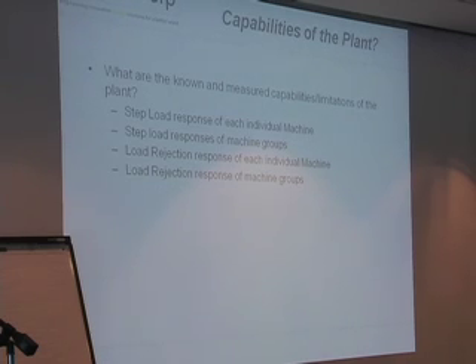And then how do they behave in different groups? We originally didn't test them in groups, and what we've found in recent years, especially with dissimilar engines and alternators, larger and smaller machines in parallel with one another, is that when asked to take or reject a big load, they can become unstable, and the system may fail just because the big machine steals all the energy, the little machine goes out on reverse power, and suddenly you haven't got as many generators on the line, so the whole system falls over.